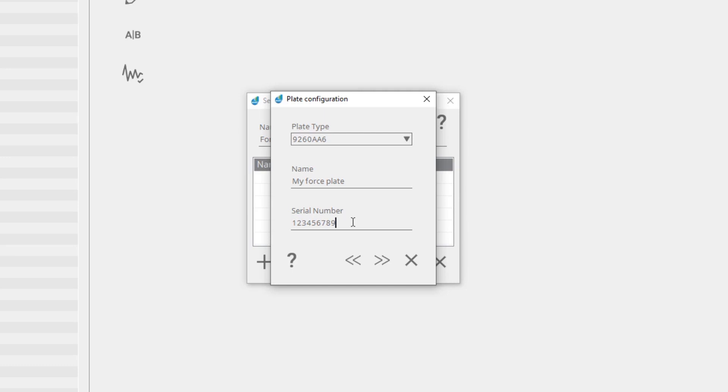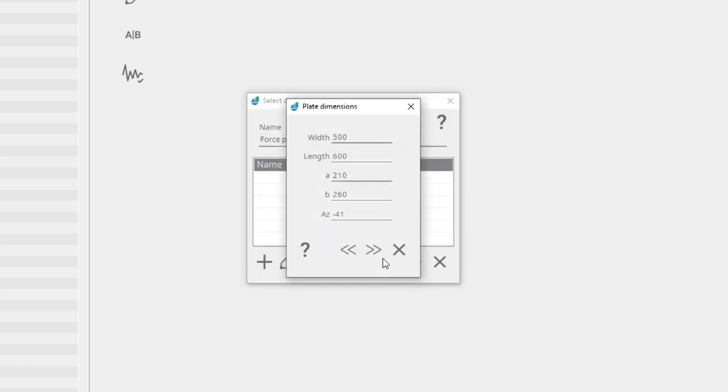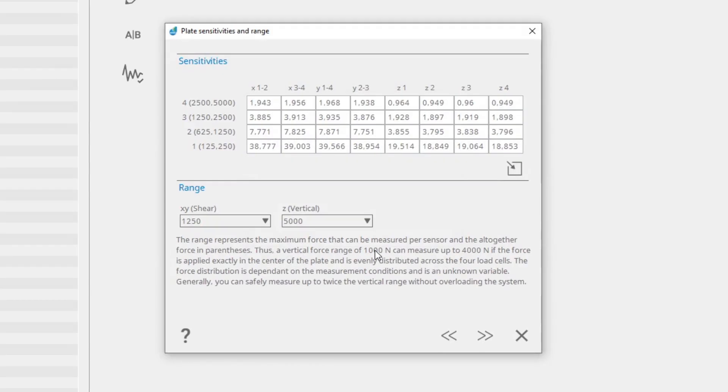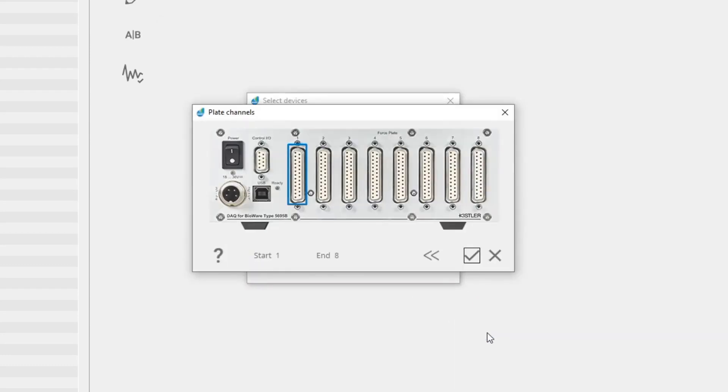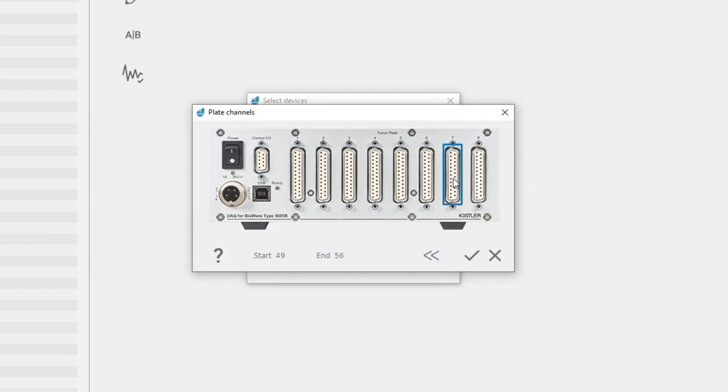In the next steps, plate dimensions, sensitivities, and range are displayed. Compare these values with the values from the calibration sheet shipped with your force plate. Modify them if necessary. Select the channels on the DAQ system to which the plate is connected.